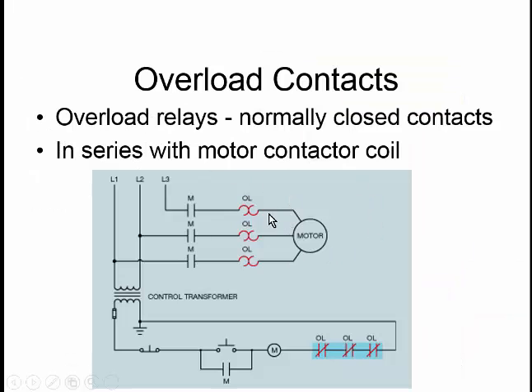So how do these work? Here's the actual overload in the schematic, the top part being power, the bottom part being control. The top might be 480 volts, and the bottom could be a small voltage, maybe 120 or 24 volts. Here's my control drawing, here's my power drawing. In the power circuit are the overload elements, the sensing elements. They do not trip the current, which could be 200 amps. What they do is cause these little tiny contacts to trip, which kills power to the control circuit, which kills power to this little coil. When the coil dies, the contactor opens and power is disconnected from the motor.